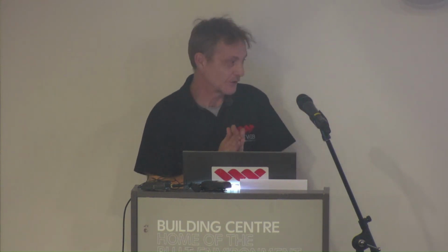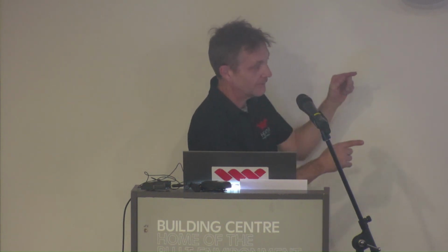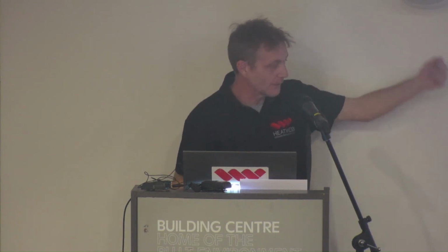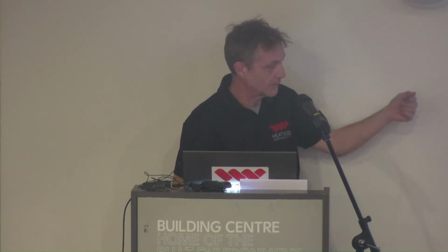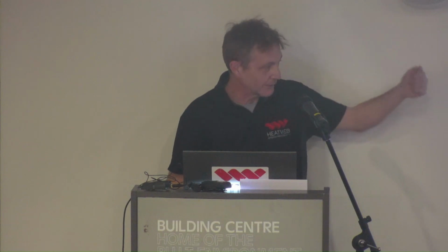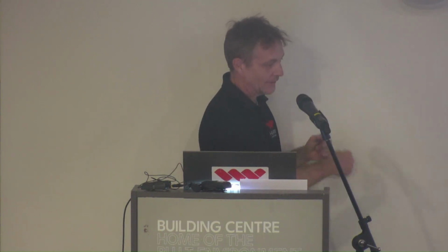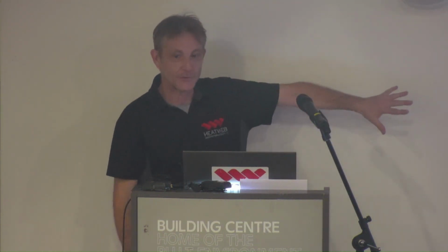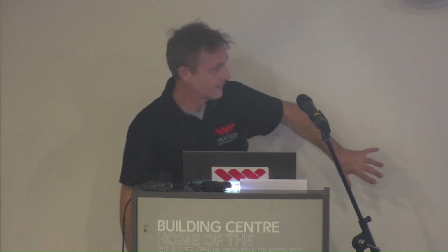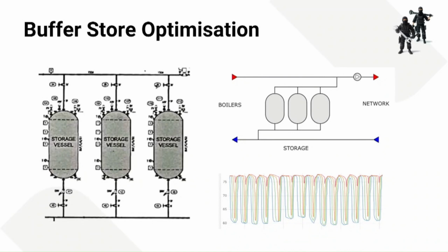This is a typical buffer store arrangement - three buffer stores in parallel. Boilers connect from the left, the load is on the right. The store on the left is getting hot all the time, charged from the boilers. The store on the right is cold because that's got the network, and the return is getting diluted. If you ever see buffer stores installed like this, it's not going to work. It might look like it's working, but it won't be working efficiently by any means - it won't be loading and discharging, as you can see in the graph bottom right.